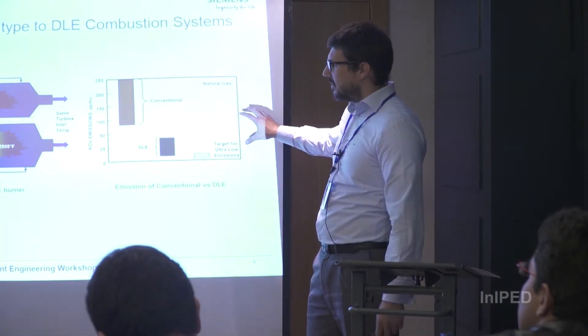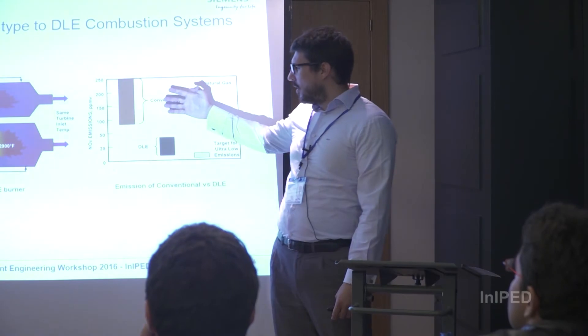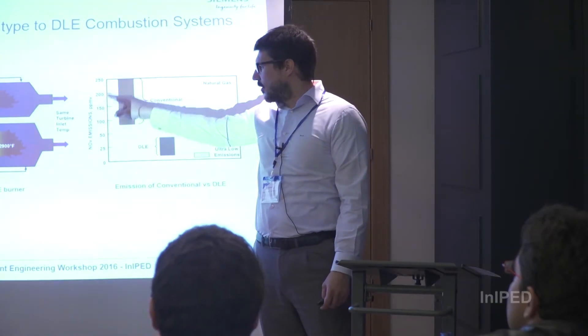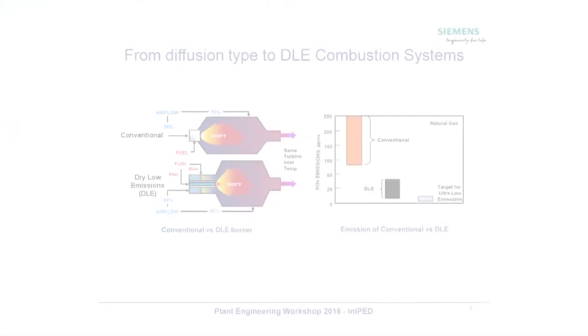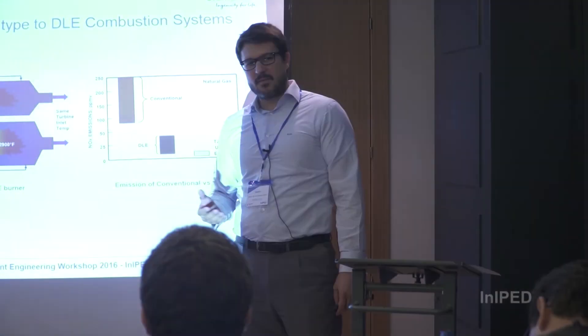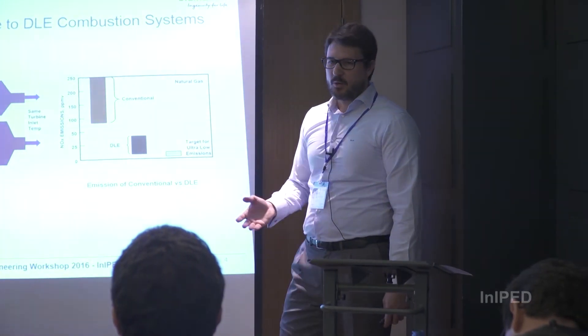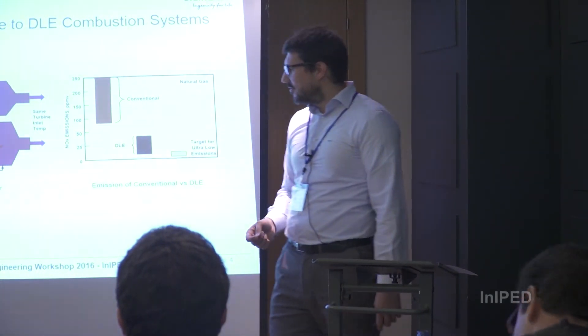Here you can see what happens on both types of combustor. With the conventional one, we are going to be in this higher range of NOx emissions. Therefore we need either water injection or an SCR at the exhaust outlet in order to comply with regulations. We are not only talking about being environmentally compatible — we are talking about complying with local regulations. This is happening now in Europe: there is a European directive that everyone has to meet 50 milligrams NOx per normal cubic meter at 15% dry oxygen.